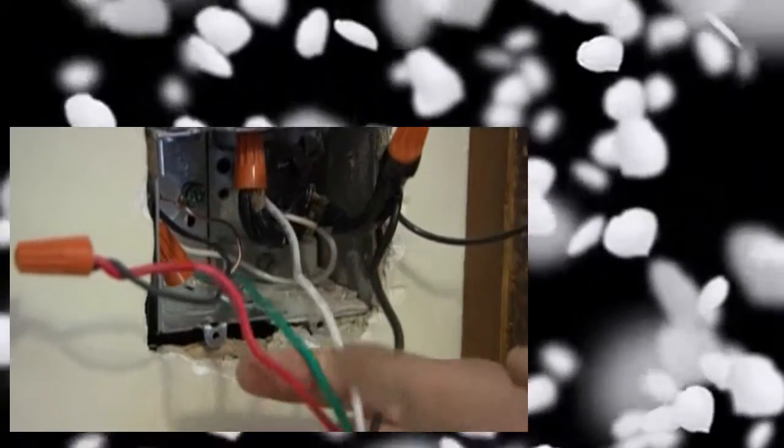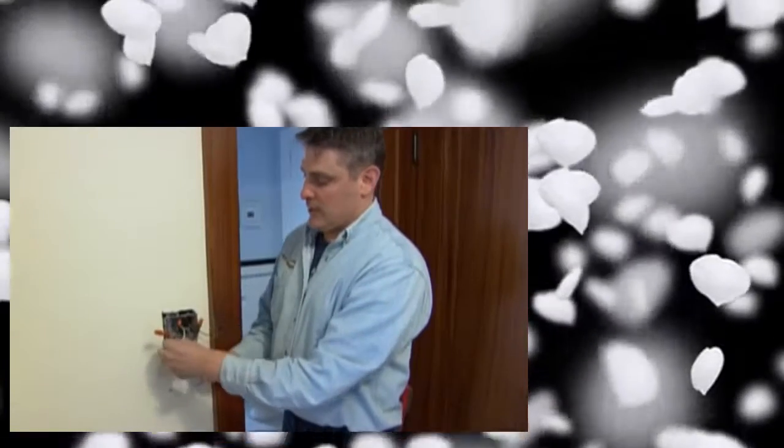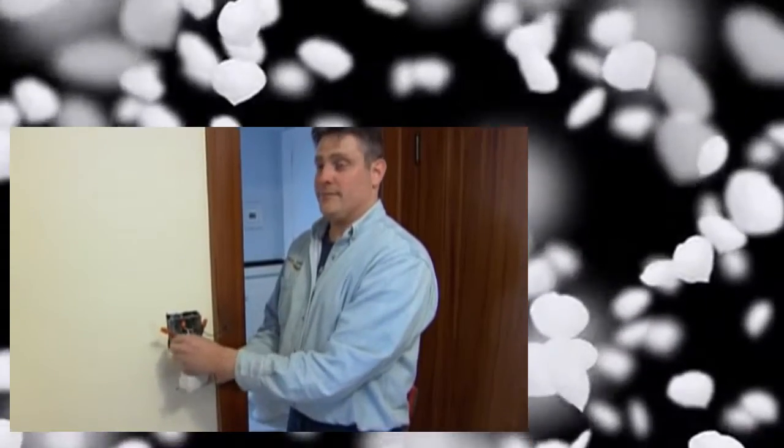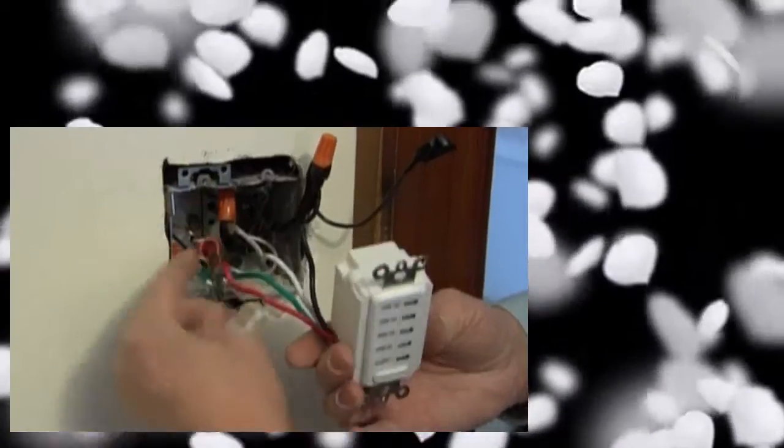We have a white wire which is connecting to the common neutral in the back of the box. And you have the green wire which is connecting to the ground wire we connected earlier to the box and a red wire which is going to your fan. Now I'll gently fold the wires back into the box and attach the switch to the wall.